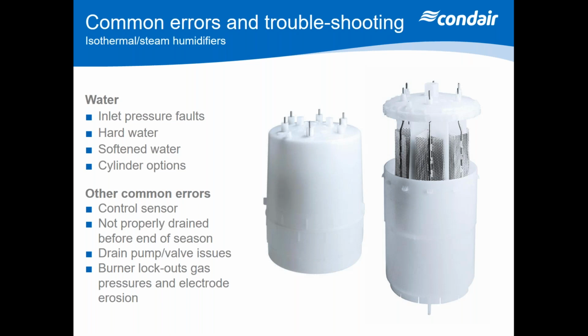Burner lockouts, we see sometimes if the units are on a roof somewhere that they're actually using inconsistent gas pressures. That's going to have an effect on the burners, and also making sure the electrodes that spark the system are actually changed on a regular basis.